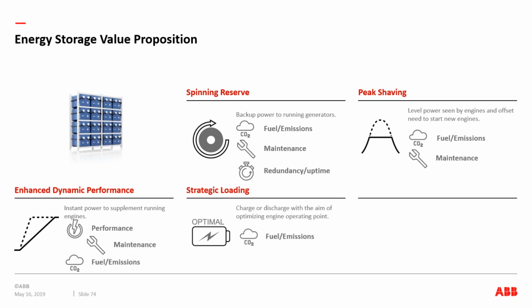Strategic loading is interesting. We already gain some benefit with a DC grid system with variable speed engines, but it's still the case that you might have a more attractive fuel consumption profile at, say, 85% MCR as opposed to 50% MCR on the engine. So if you want to take advantage of that more attractive fuel consumption profile at higher power, you can use the batteries: operate my generator for a while at high power even though I only need 50% right now, charge up the batteries, then shut the engine off and use those batteries when needed, bringing the engine back online when it's time to recharge. Strategic loading helps determine how you load the engines, and the power management system handles all of that automatically for the operator.